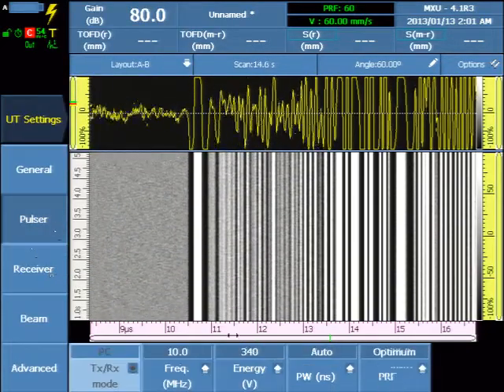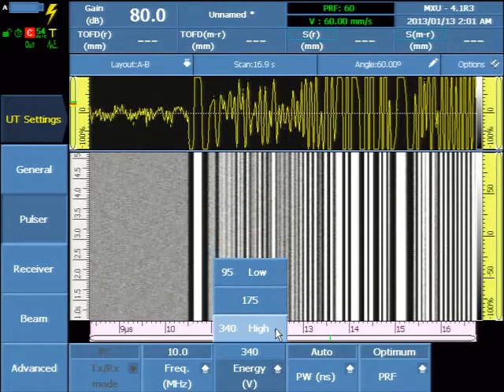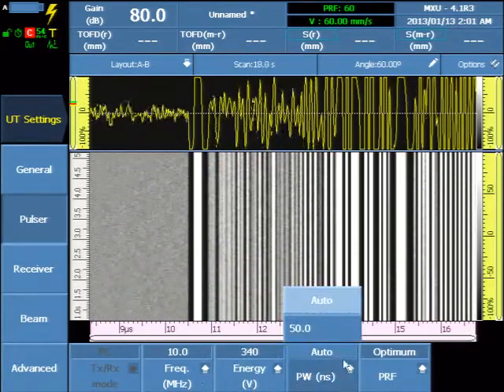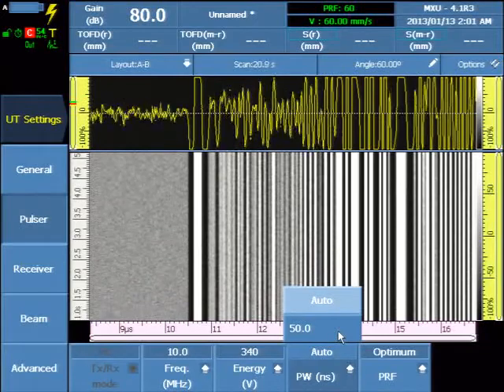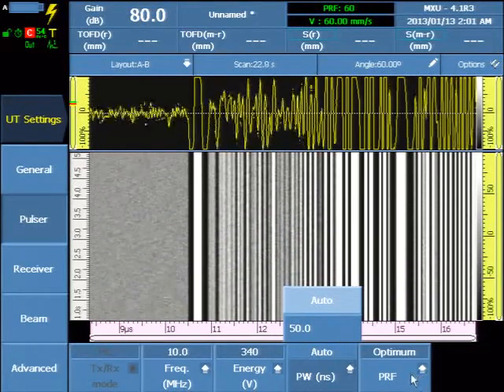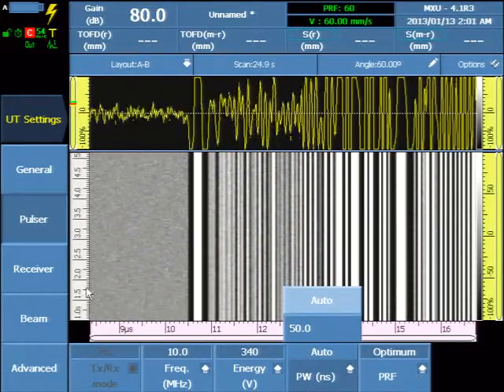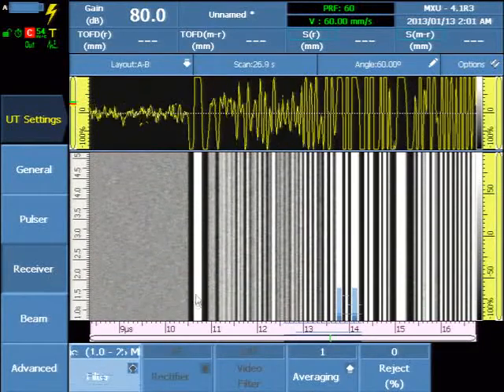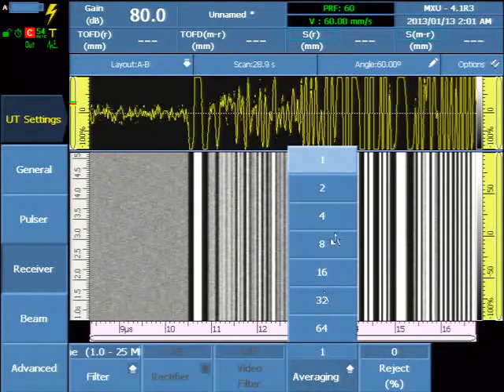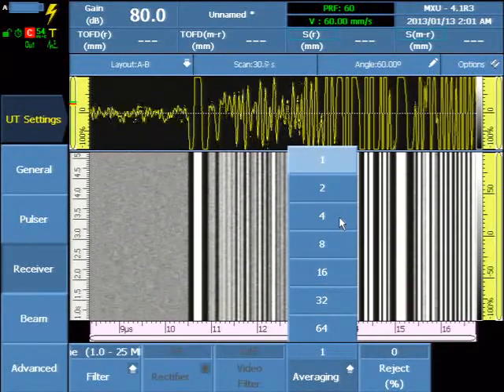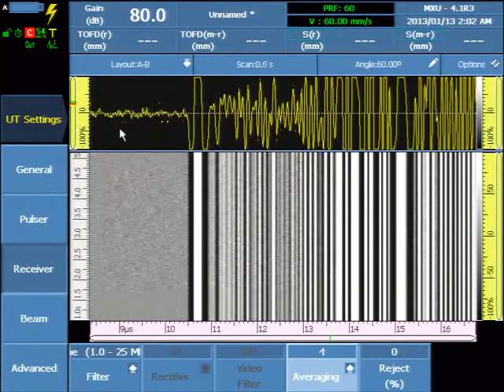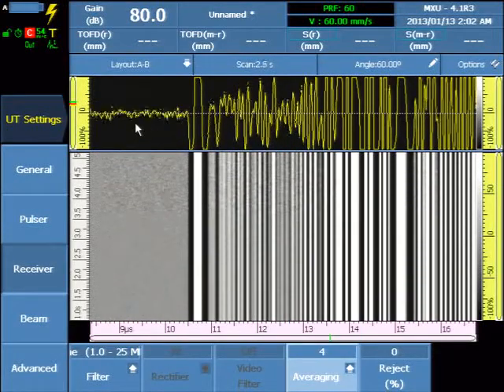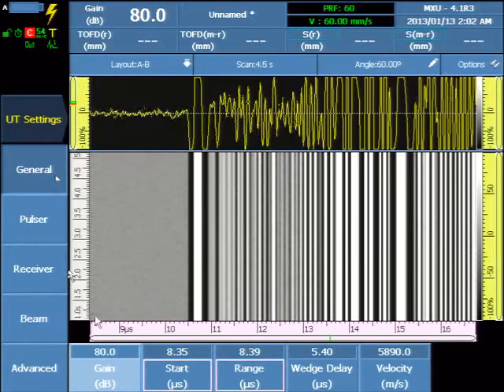Select the Pulser and ensure the voltage is on high. The Pulse Width was automatically determined by the probe frequency, and the PRF set to Optimum. Under the Receiver tab, select an averaging factor of either 4 or 8, or however much is necessary for best results.